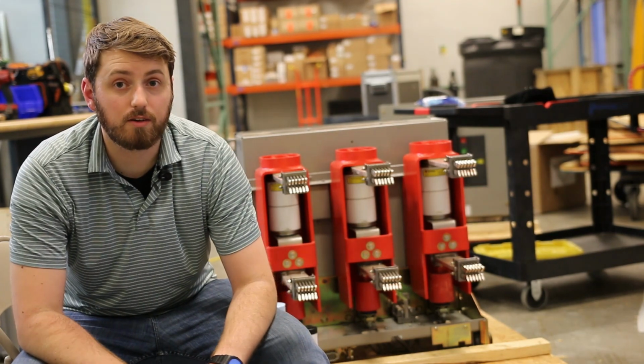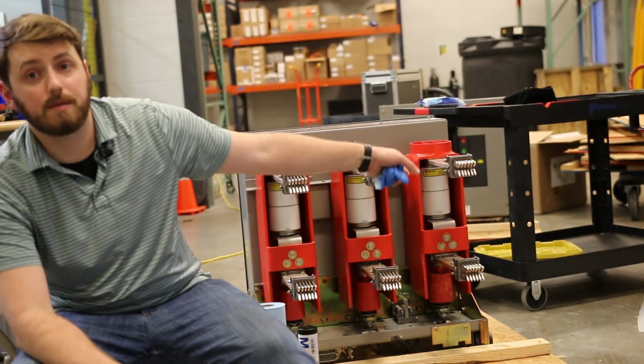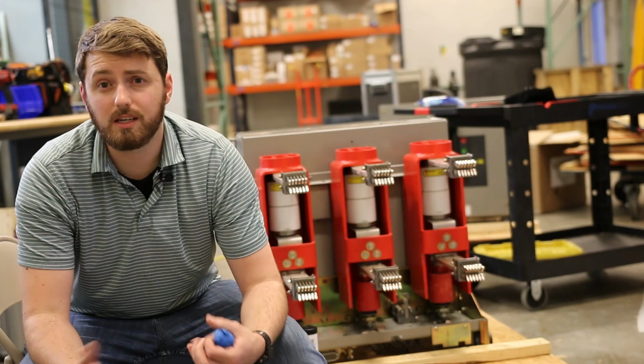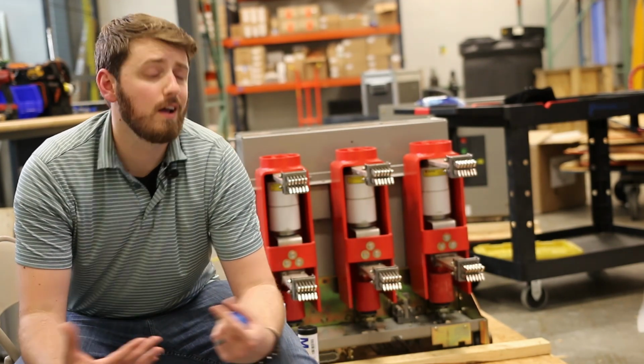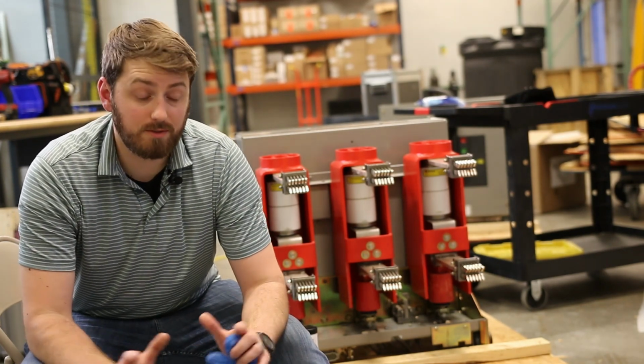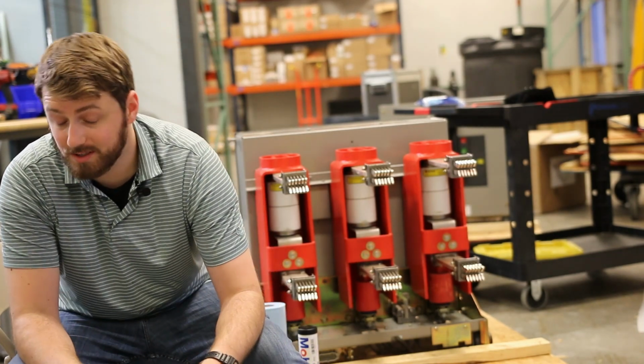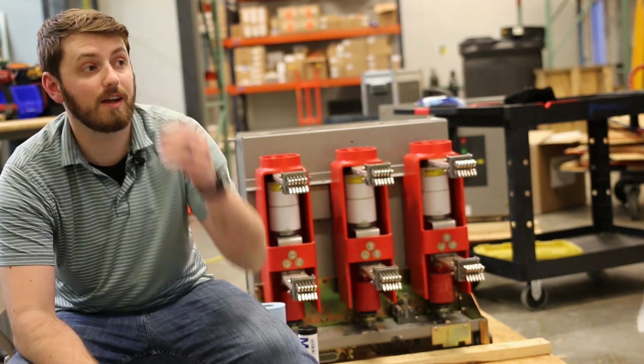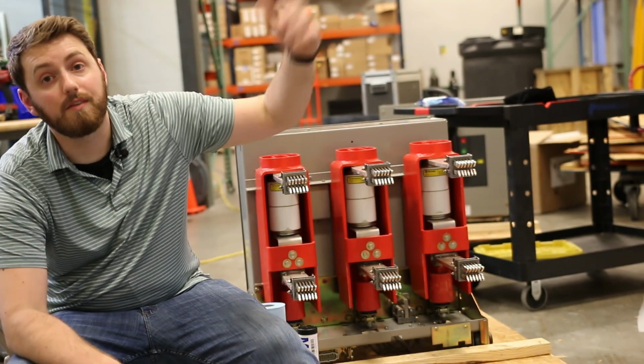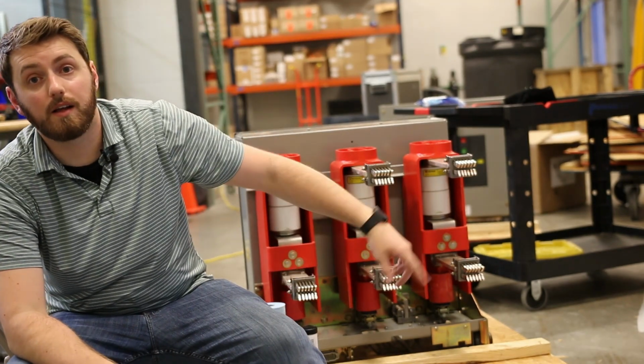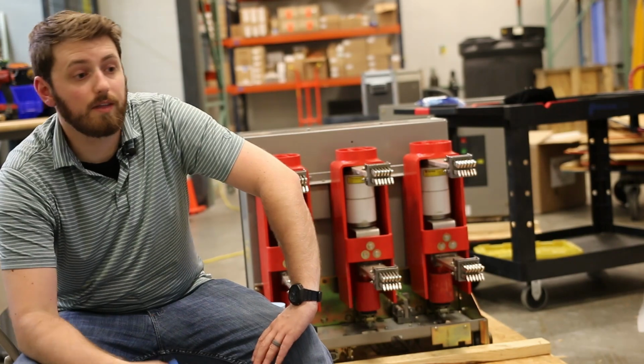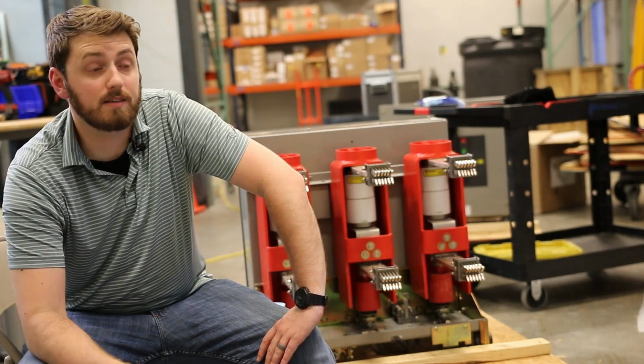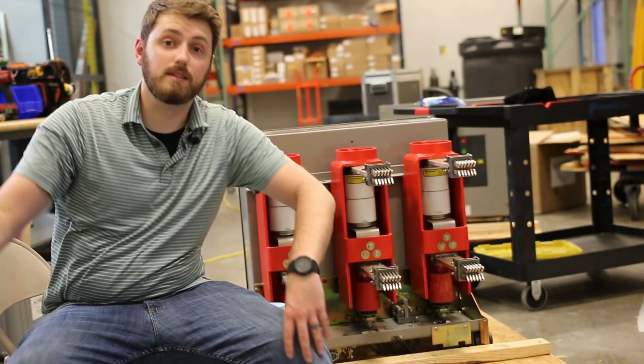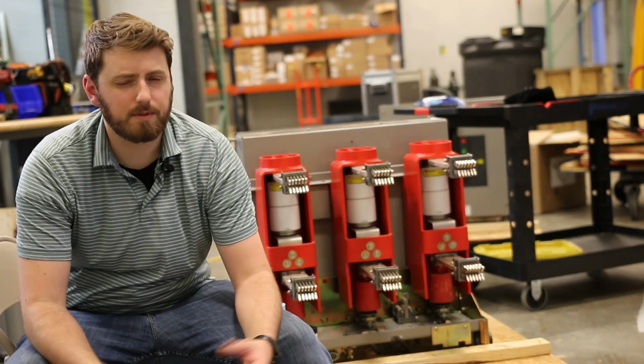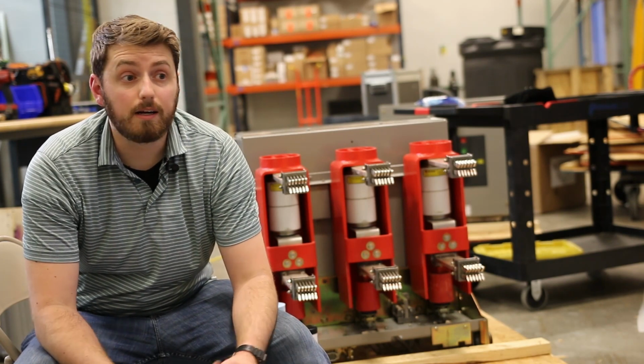A couple caveats that you're gonna run into. The breakers sometimes have an internal undervoltage relay that you'll need to defeat. There's a couple ways around that. Don't be afraid of reading the manual. The manuals are intimidating, and on newer stuff, they're a lot longer. Sometimes they're harder to find, but everything you need to know is gonna be in there. The contact gap is gonna be different for every breaker. The voltage that you need to high pot them at is gonna be different. Sometimes they'll say you can only use DC, sometimes you can only use AC, sometimes you can do both. So definitely read the manual before you get into it.